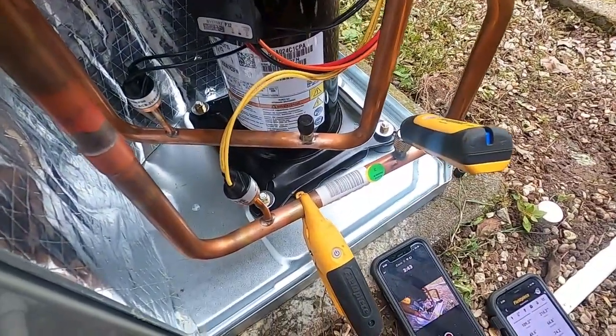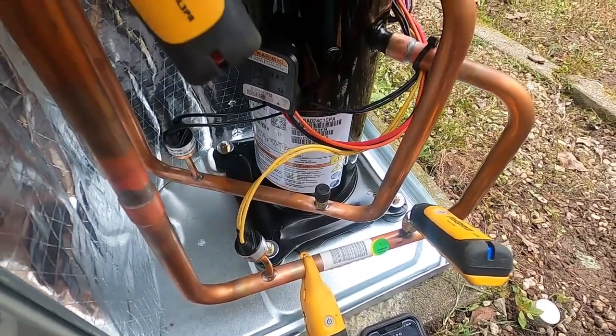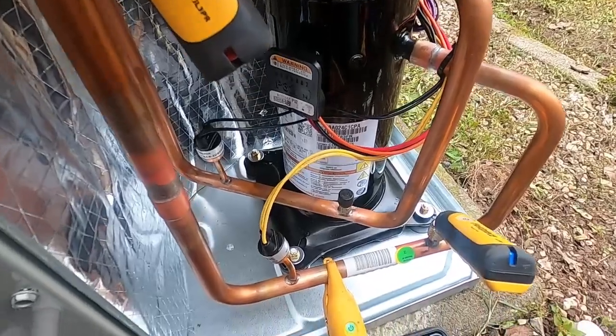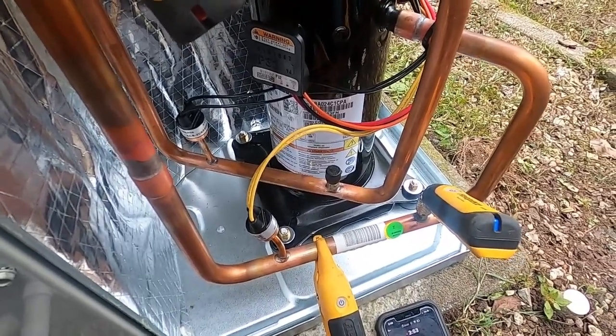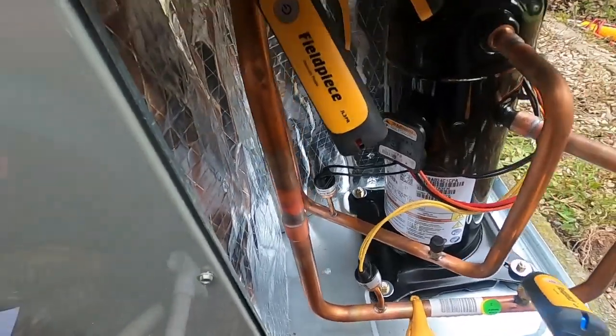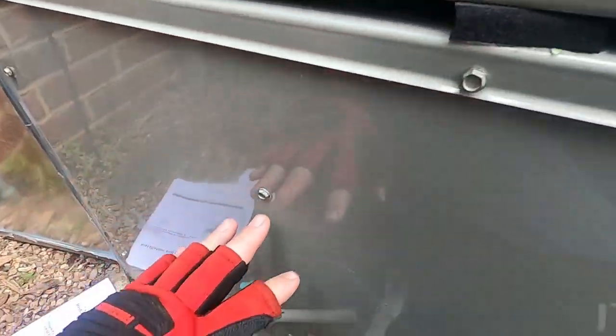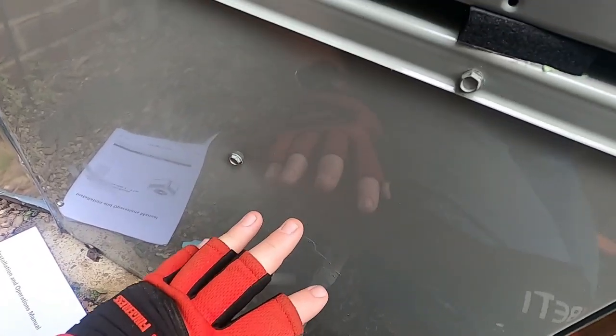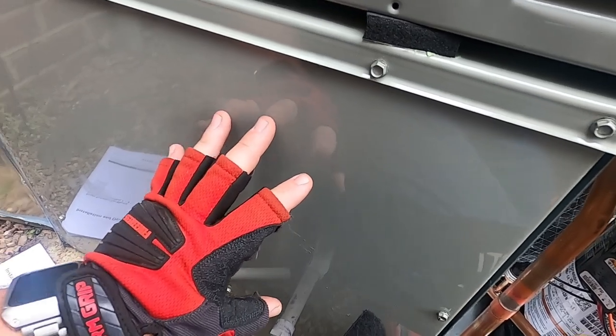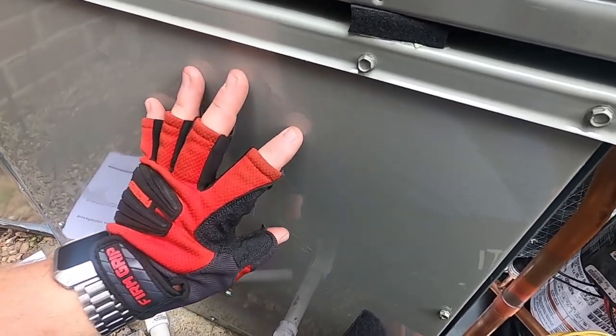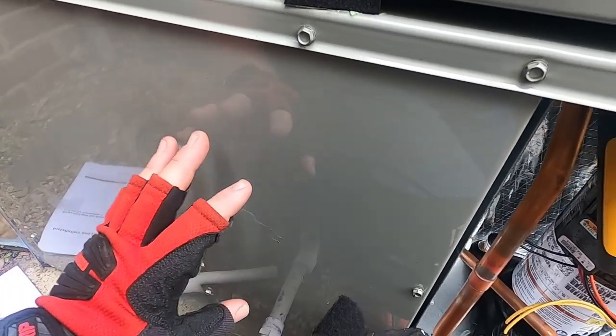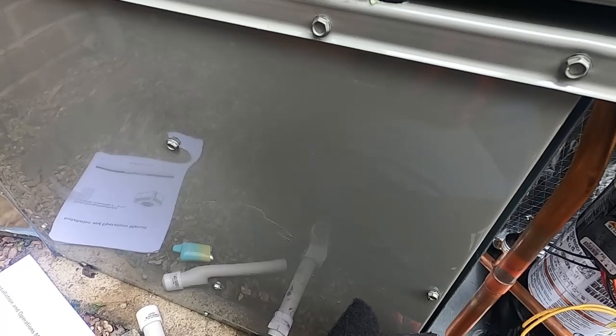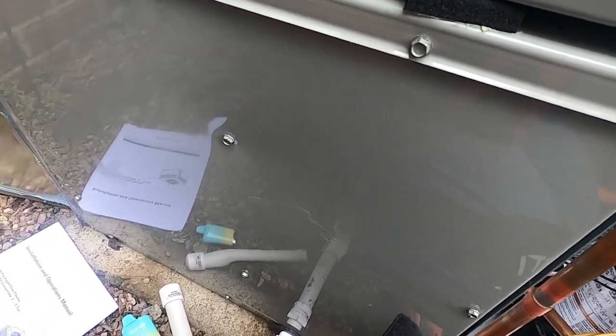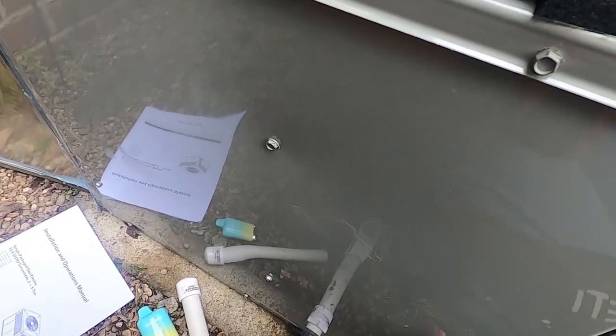So anyway, guys, this is all because of a leaking micro-channel coil that the manufacturer cannot get their hands on. Go figure. Apparently, this one has the micro-channel in it. You saw that. They have them at the factory to assemble a new system, but they don't have one to replace one that's leaking. That doesn't make sense to me. Just because one of your supply houses or none of your supply locations have one, you're putting them together at the factory. Get one from there.